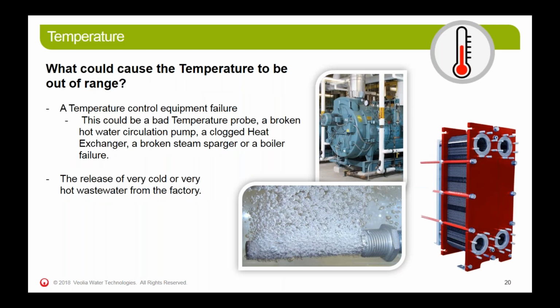So what could cause the temperature to be out of range? It takes a lot of energy to change the temperature of the water, so this isn't as likely as the pH control problems are. And most likely, a temperature problem is due to an equipment failure. This could be a bad temperature probe. I haven't seen that very often because they're pretty hardy pieces of equipment. It could be a hot water circulation pump that's bad, or a clogged heat exchanger, or a steam sparger that's broken, or even a boiler failure. Or it could be a release of very hot or very cold water from the factory that was unusual. Next.